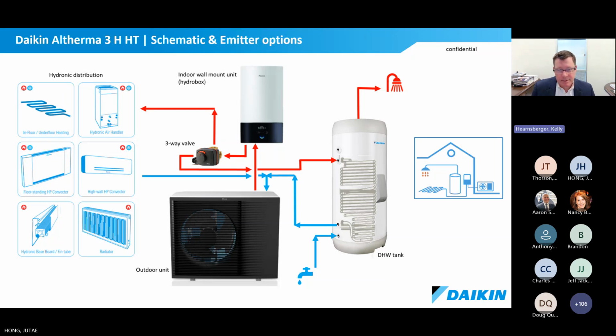So that's kind of the system play, the architecture. Again, a reminder: the plate heat exchanger producing the hot water is in the outdoor unit. There is no refrigerant flowing from the outdoor to the indoor. It's all encapsulated in the outdoor, so it is a package unit, for lack of a better definition, and there's no refrigerant work required to install this system. So we'll talk later about the challenges of whether it's a plumber installing this or a heating and cooling company, or that's something we'll have to address. But that's how the system works.